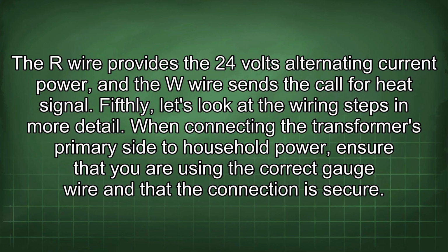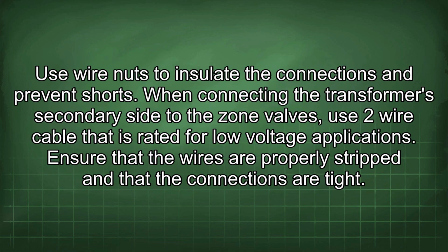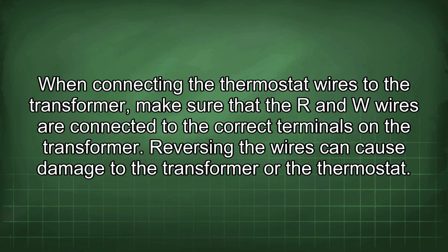When connecting the transformer's primary side to household power, ensure that you are using the correct gauge wire and that the connection is secure. Use wire nuts to insulate the connections and prevent shorts. When connecting the transformer's secondary side to the zone valves, use two-wire cable that is rated for low voltage applications. Ensure that the wires are properly stripped and that the connections are tight. When connecting the thermostat wires to the transformer, make sure that the R and W wires are connected to the correct terminals in the transformer. Reversing the wires can cause damage to the transformer or the thermostat.